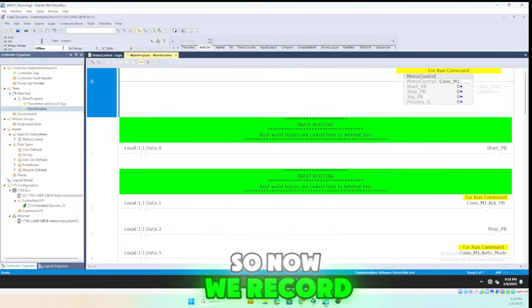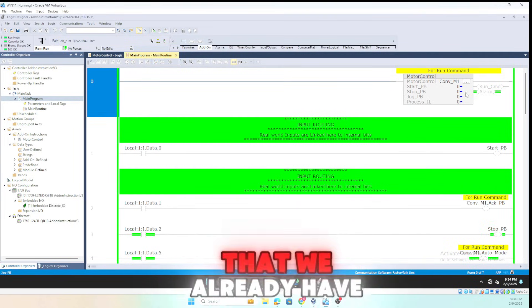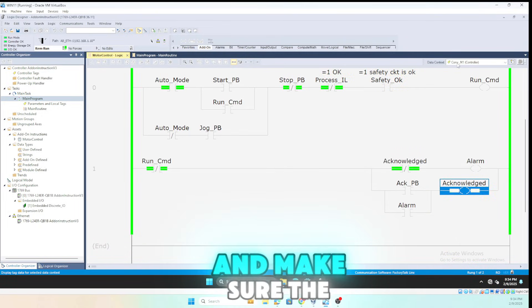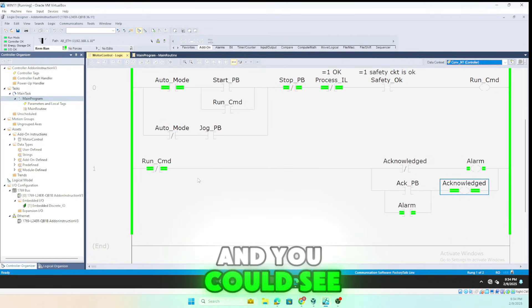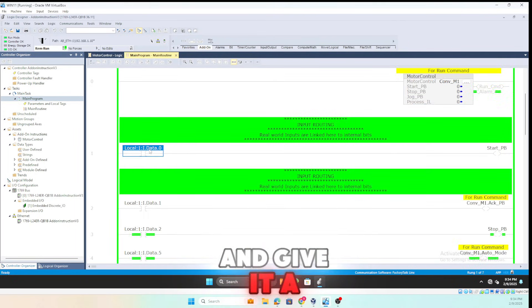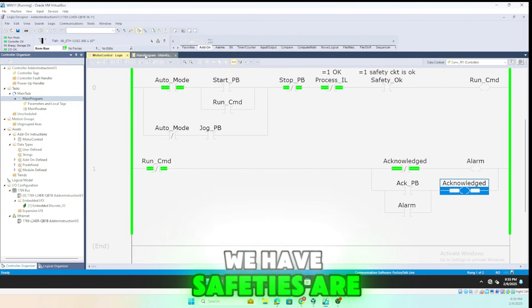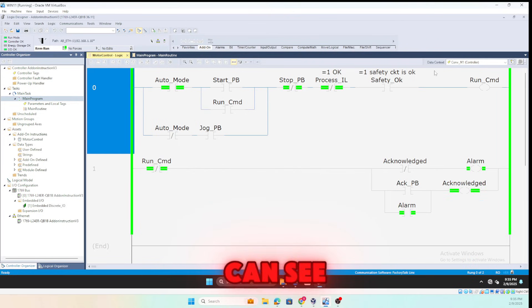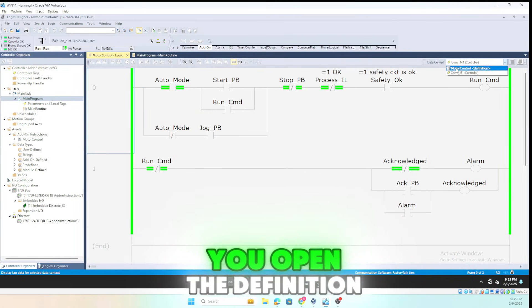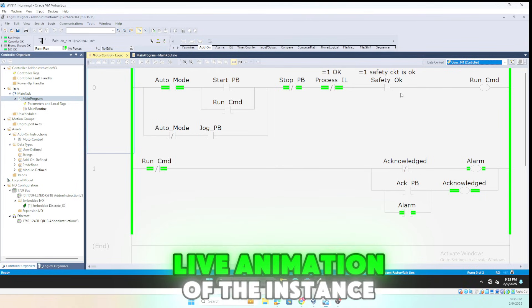We find the PLC, download the program, and go back to remote run. We already have an alarm because the machine is not running — since we don't have a run command an alarm is active. To see what's happening, right-click and open instruction logic, then make sure the context is set to the conveyance instance. You can see the live animation. Note: if you open the definition it will be grayed out, but if you open the instance you'll see live animation of that specific instance.